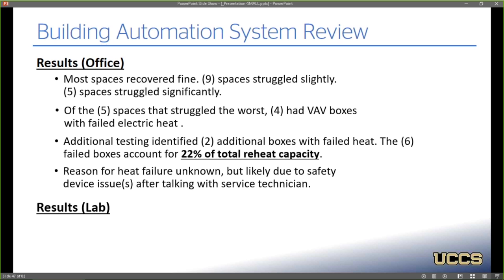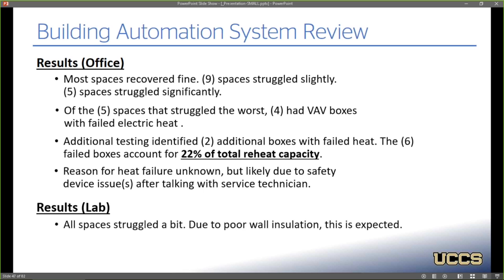So the results at the lab, all of the spaces struggled a little bit, and I'm guessing that's due to the poor wall insulation, and one of the zones has a pretty good size roll-up door, so that's kind of expected. Poorly insulated buildings just simply have a much harder time recovering. So there's likely still some opportunity there, but maybe instead of going back to 55 degrees, we go to 60 or 62. That's still better than running things all the time.